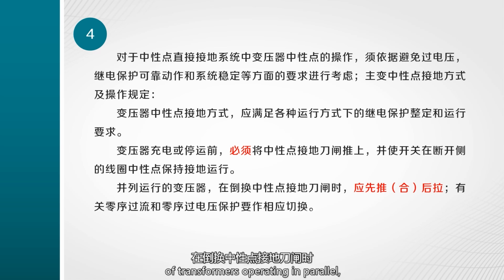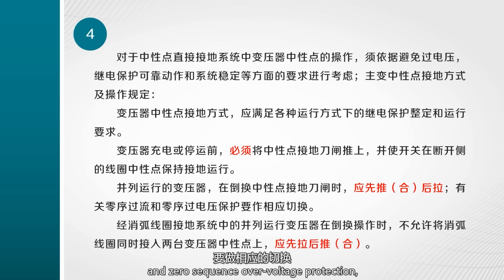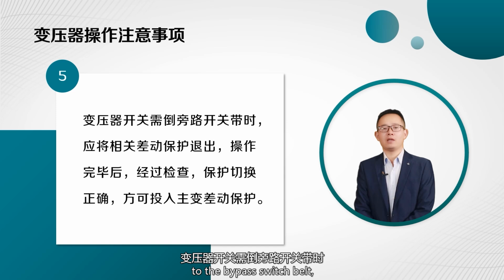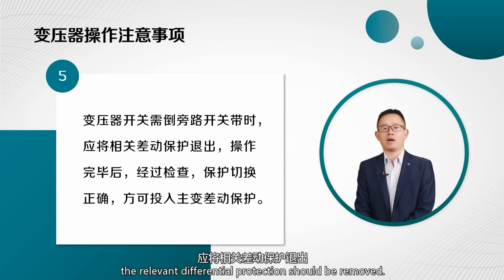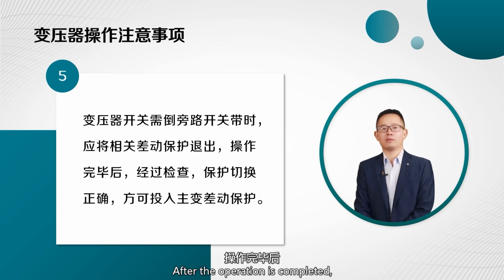When switching the neutral grounding switch of transformers operating in parallel, they should be pushed first and then pulled. Corresponding switching should be made for zero sequence overcurrent and zero sequence overvoltage protection, and the parallel operating transformers in the arc suppression coil grounding system should be switched. During the switching operation, it is not allowed to connect the arc suppression coil to the neutral point of 2 transformers simultaneously. It should be pulled first and then pushed. When the transformer switch needs to be switched to the bypass switch, the relevant differential protection should be removed. After the operation is completed, it should be checked that the protection switch is correct before the main transformer differential protection can be put into operation.